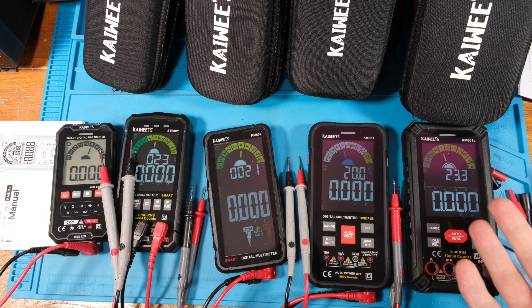Okay guys, we have the Big Bad X-Tech insulation tester. I've got it in this mode here. It's set for 500 volts and we're plugged directly into this little guy here. It says it's good for 600 volts, so 500 volts should be fine. Now let's put it in auto mode and see if it can detect what's happening to it. Kind of mean, right? Well, right now it thinks it's reading ohms out of this. Okay, let's go ahead and apply the volts.